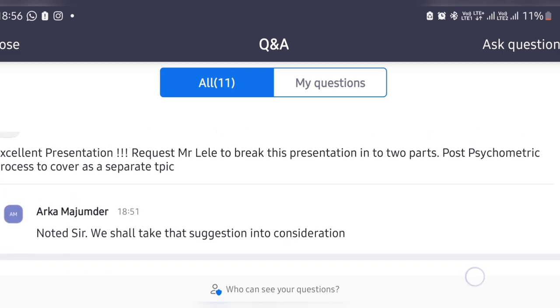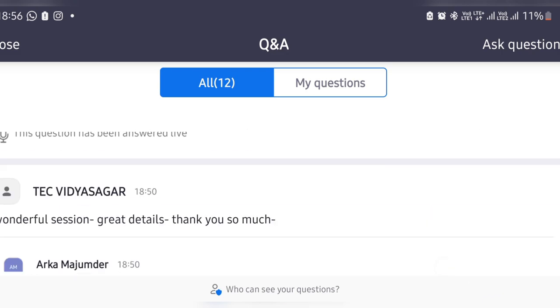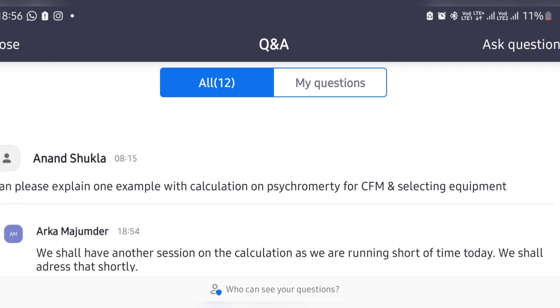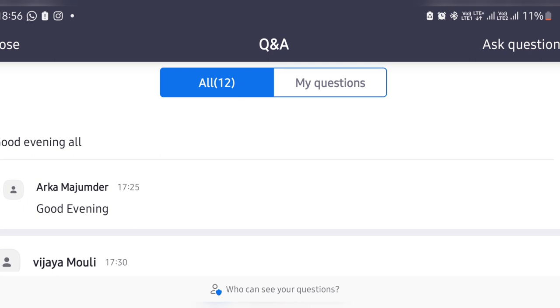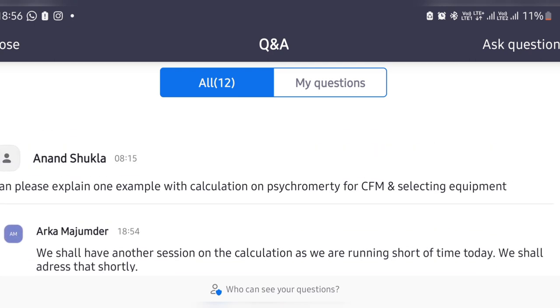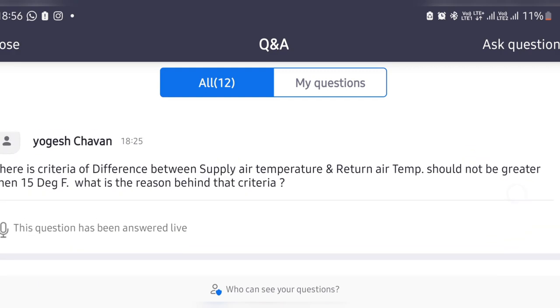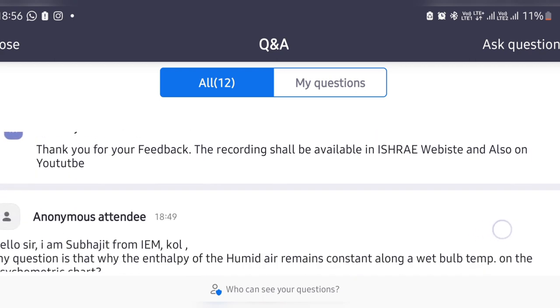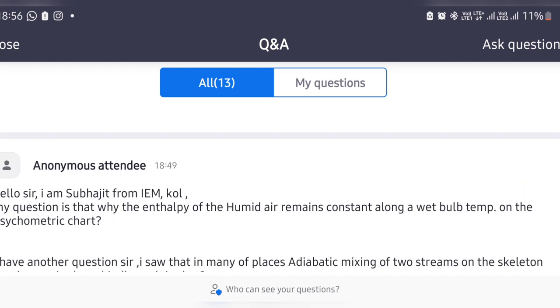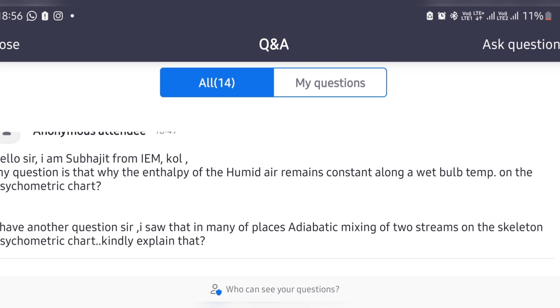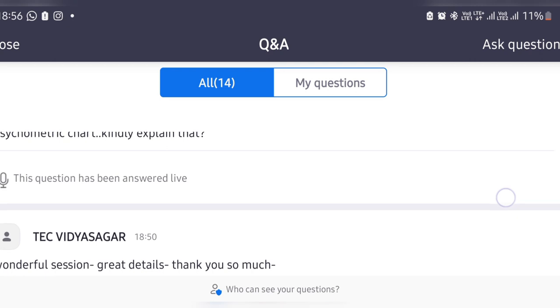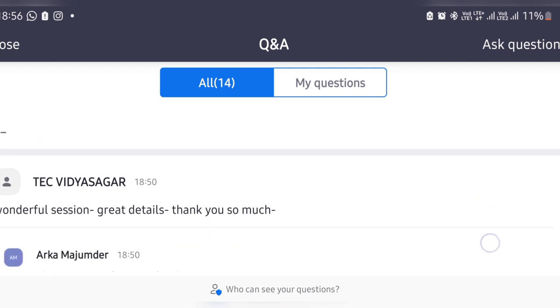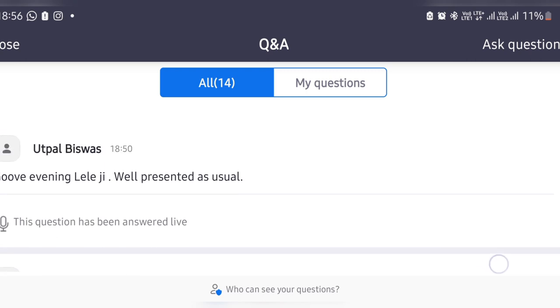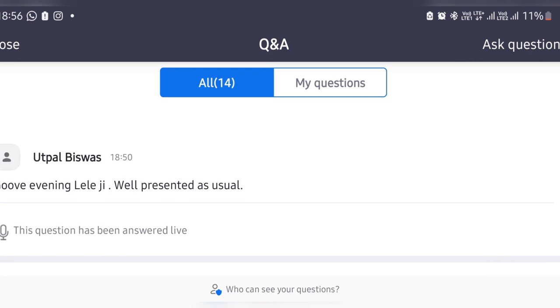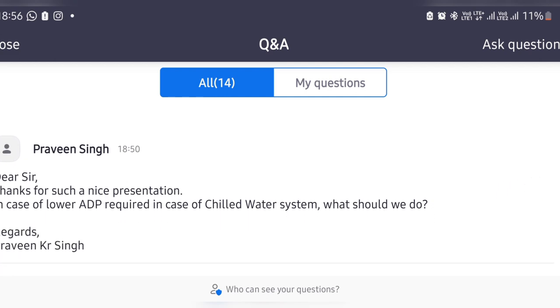First of all, we need to understand there are some spaces where you have lower ADP, which is dictated by the space. Now, your chilled water system design, many times what I have seen is a thumb rule is followed without giving due consideration to the spatial requirements. Now, what I had seen in some systems where we came up with ADP requirement lower because the space was demanding. And personally, I feel that each space should be given its due respect. And that's the reason we need to do each room analysis, at least each space.